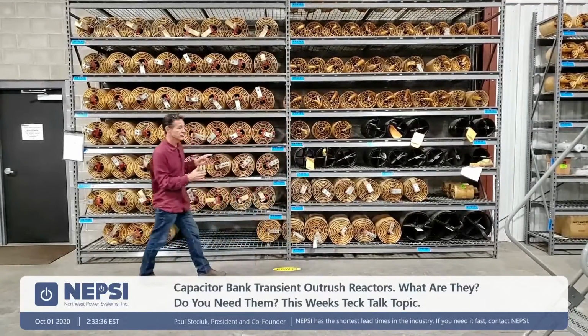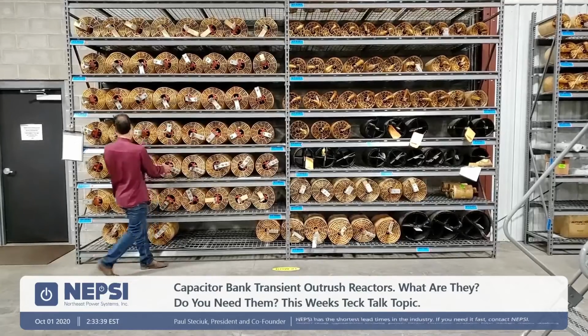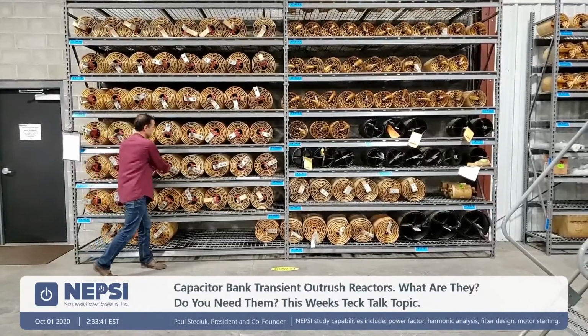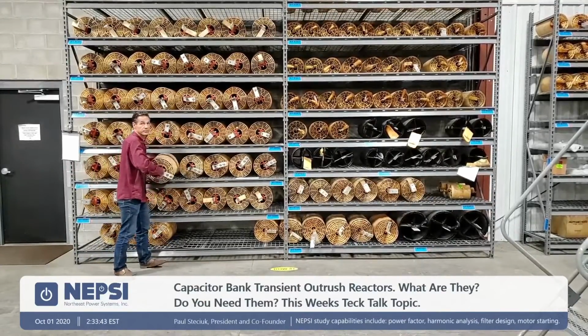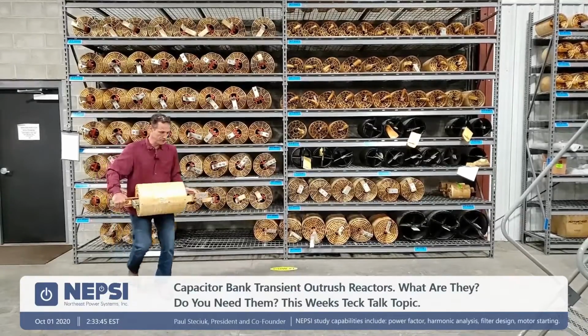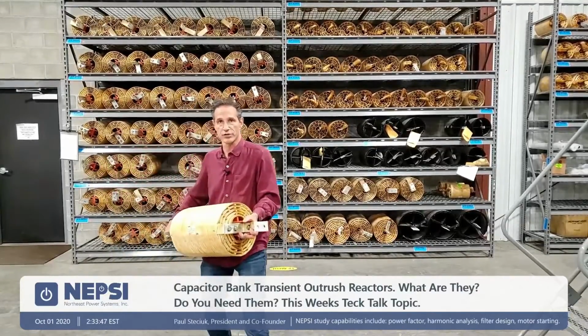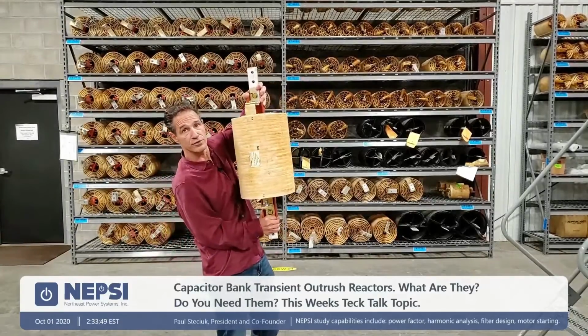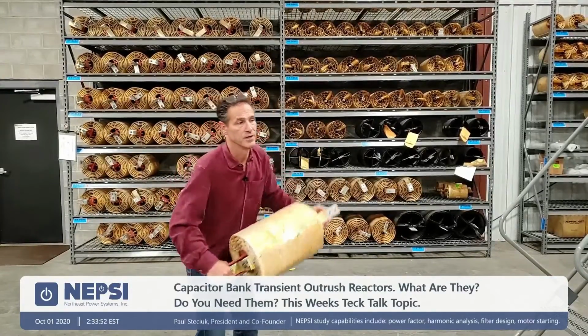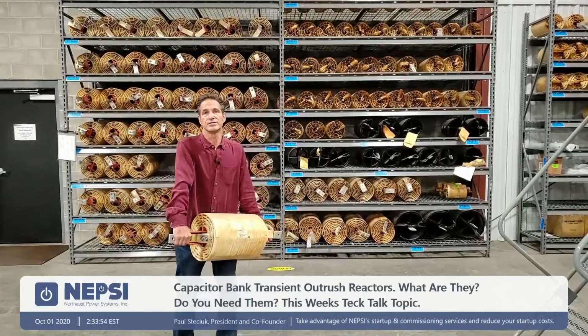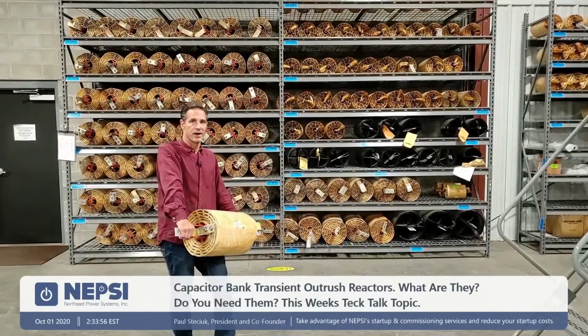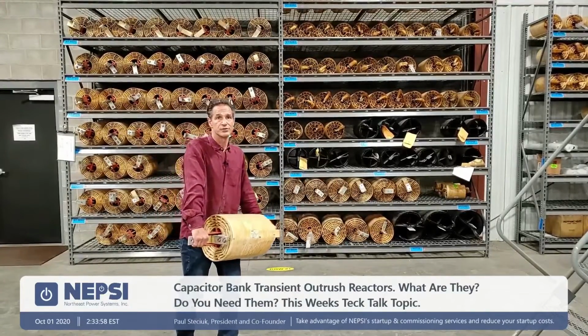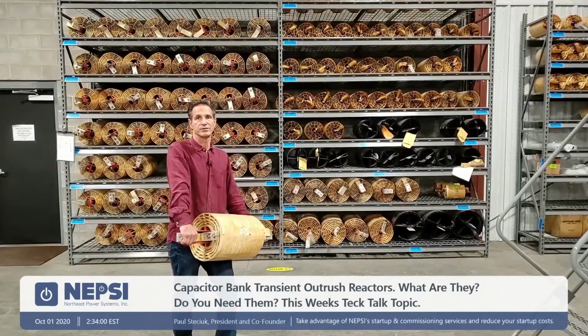I got a whole rack of transient inrush reactors here, and this particular transient inrush reactor is 47 microhenries and 300 amps. So 47 microhenries, 300 amps. You can see kind of the construction. We put this into the bus bar structure of the capacitor bank, and normally it's put on each stage, and it limits the back-to-back transient current associated with back-to-back switching in the capacitor bank.